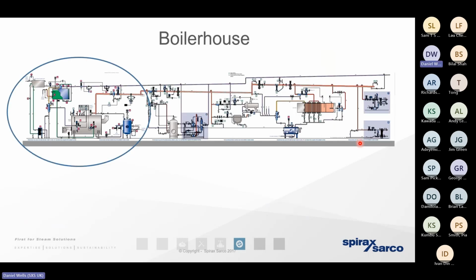So last week we looked at the boiler house in some considerable detail to understand the best practice we need to employ at the point of generation to control the steam boiler correctly and to ensure that not only are we producing steam rapidly whenever there's a demand, not only are we producing the steam efficiently by not consuming too much gas or producing too many carbon emissions, but also to ensure that we're producing the best possible quality and condition of steam.